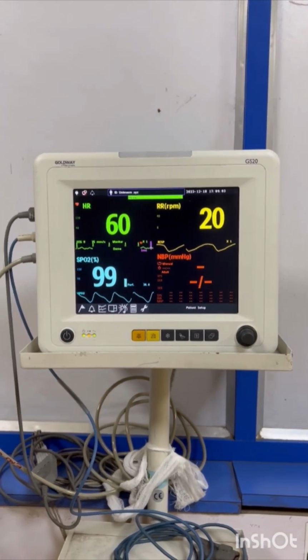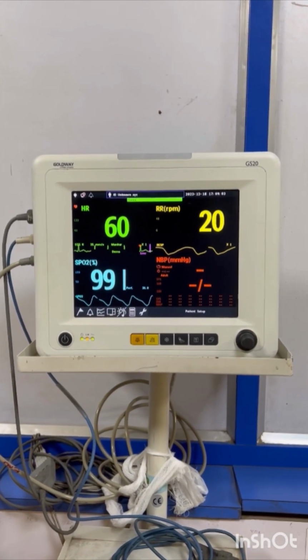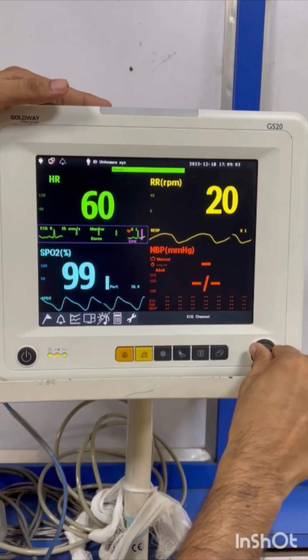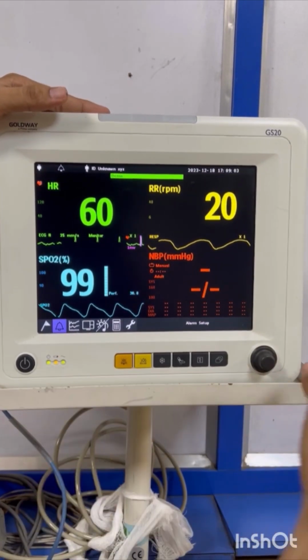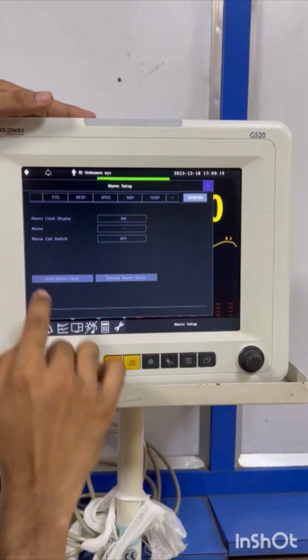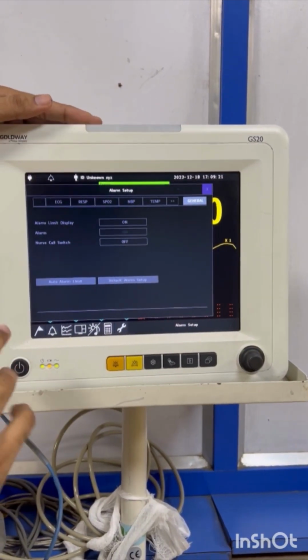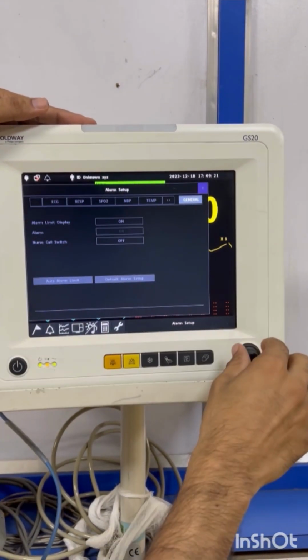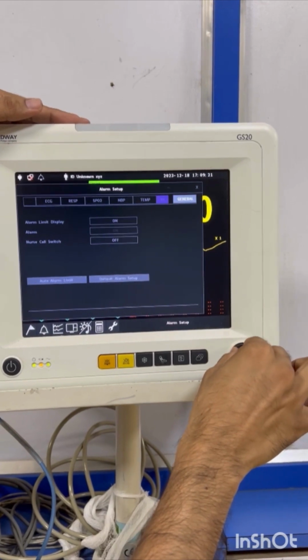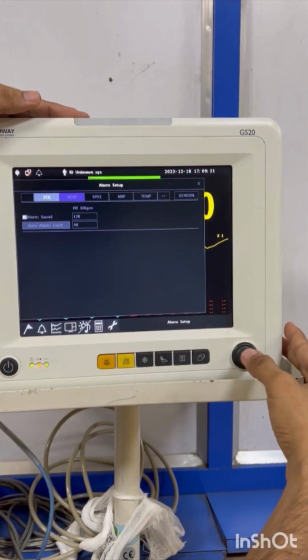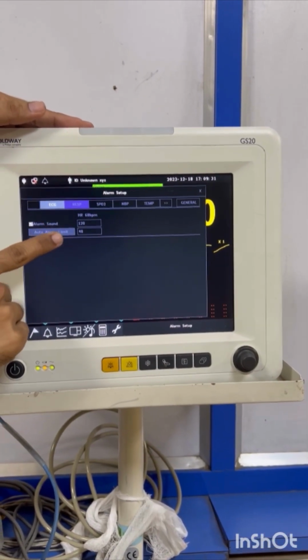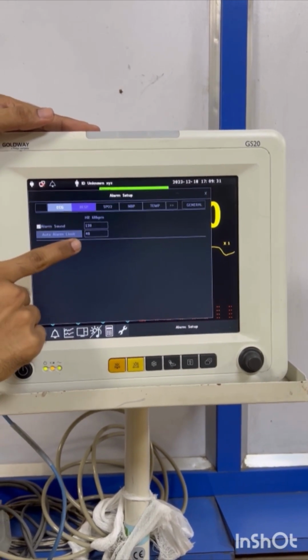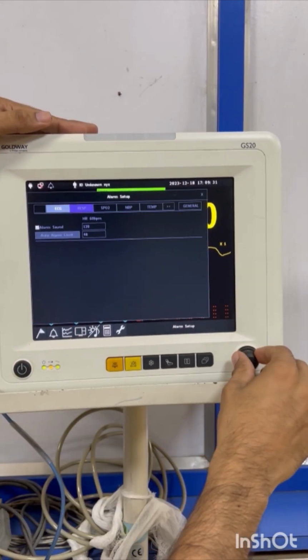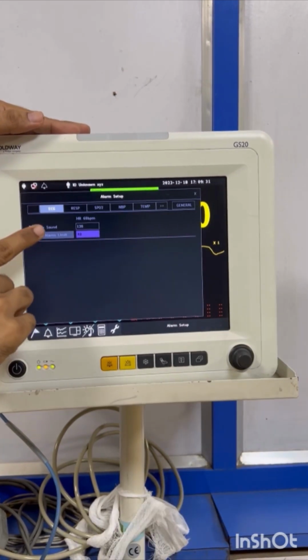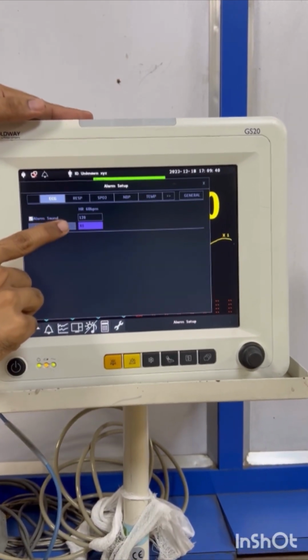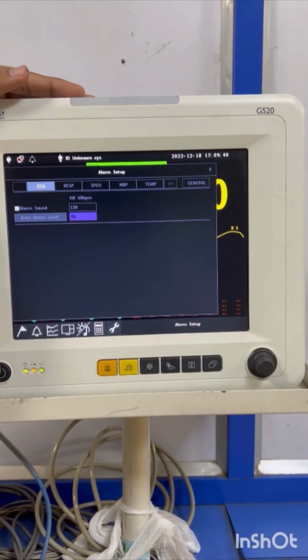Second thing is how to set alarm limits and alarm volume in patient monitor. So I'll go to the bell icon, I'll single press it. From here you can adjust all the alarm limits. For example, for ECG, respiratory, you have to go to each parameter. I'll go to ECG. Here you can see higher limit and lower limit. So you can change higher limit and lower limit according to the patient condition. So if patient heart rate exceeds 120 beats per minute, the monitor will give alarms.